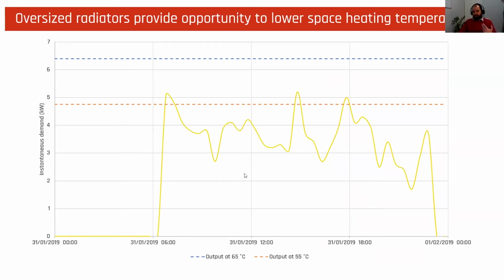So this is where we're dropping. The yellow line is the output from a radiator, the demand in a flat heating. And this was during a day where it was about -2, -3 outside. And you can see that the installed capacity, the blue dashed line, the design temperature, is about 6.5 kilowatts. And that dwelling actually was really only drawing about 3.5 to 4 kilowatts.